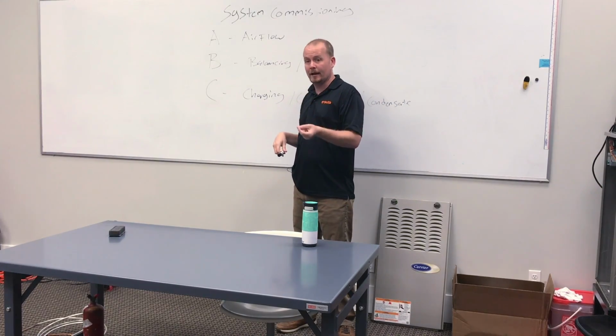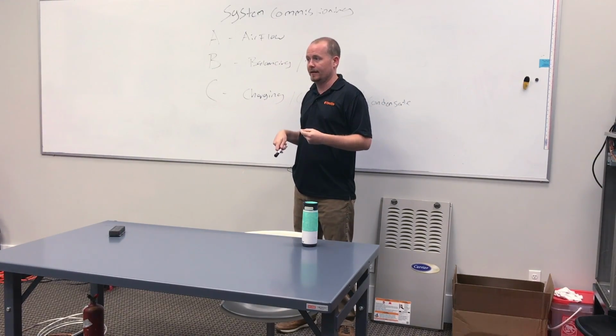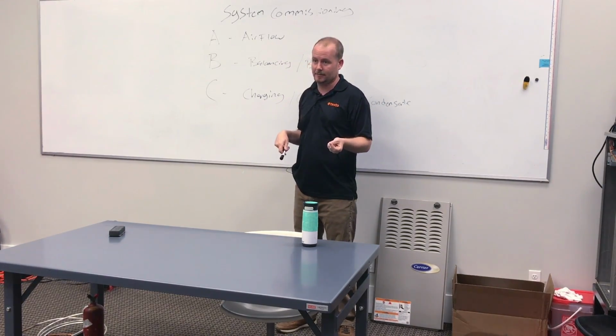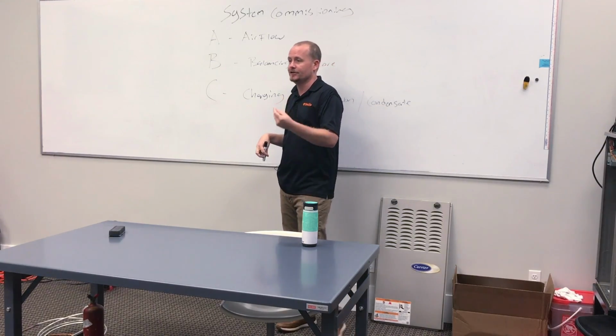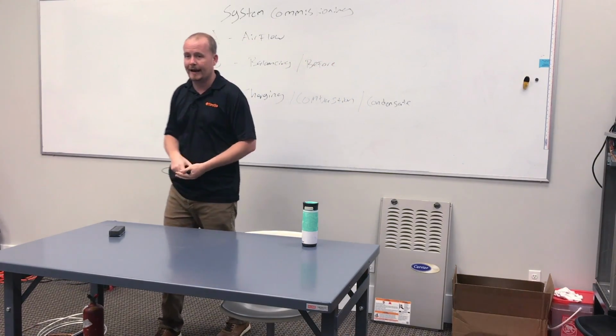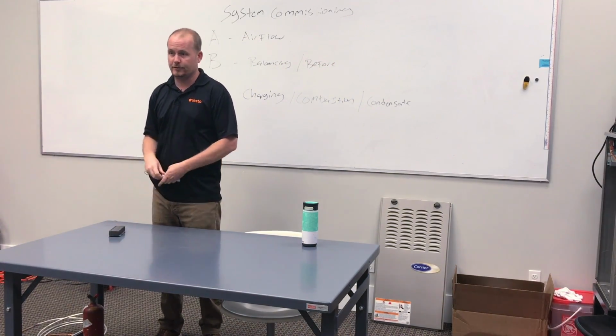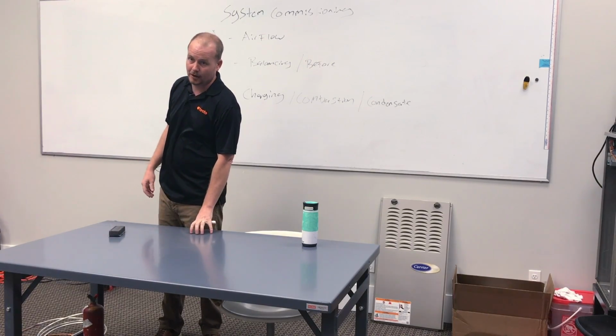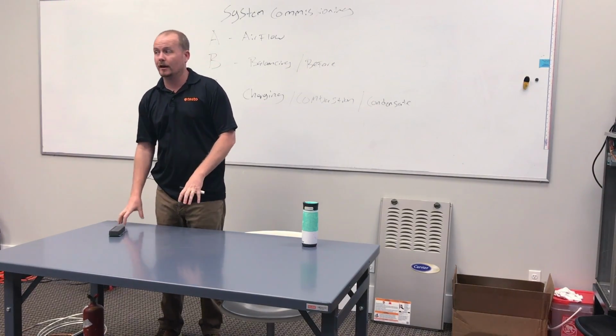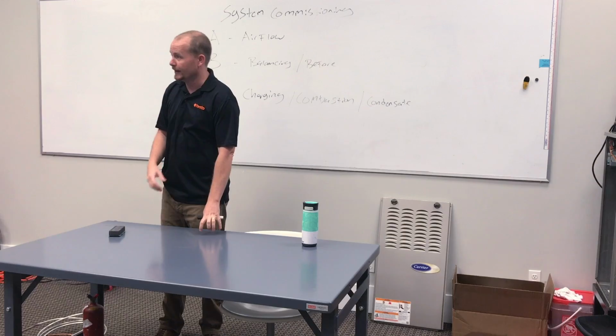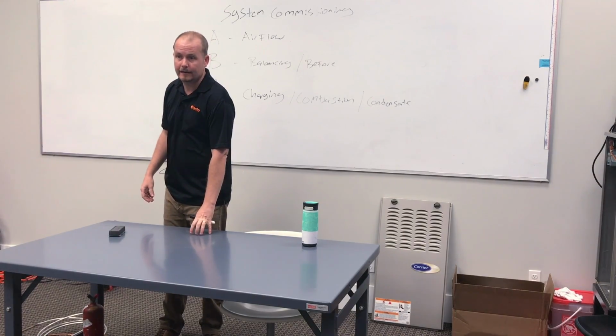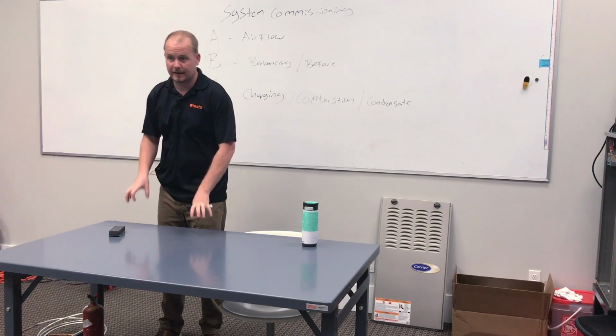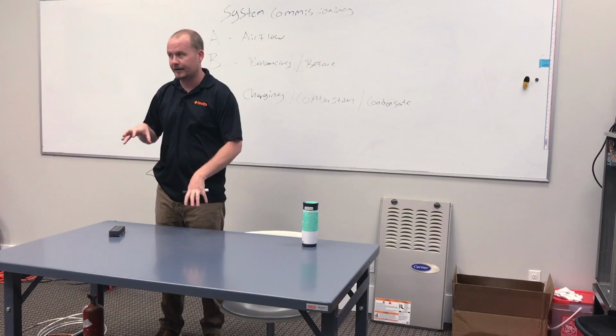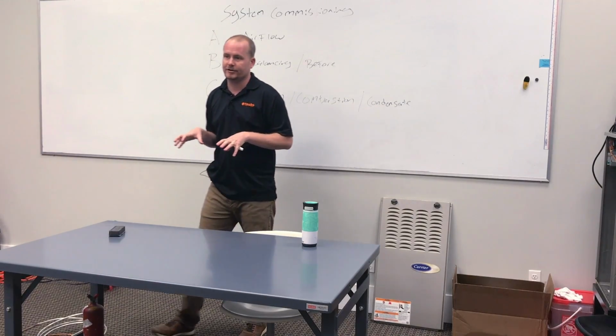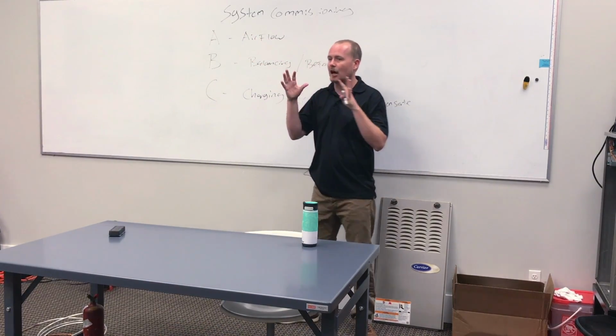And I know it's annoying, but it's less annoying than having to keep going back with a cranky customer. Because now you can have a very educated conversation and you can say, well, you did have 150 CFM in this room, and when we were done retesting, you had 175. Well, I'm still not comfortable. Okay, we'll see if we can get it up near 190, 200, but that's really the most that we can give it without stealing from other areas. It gives you a conversation that you can have with the customer. And all that's very logical conversation.